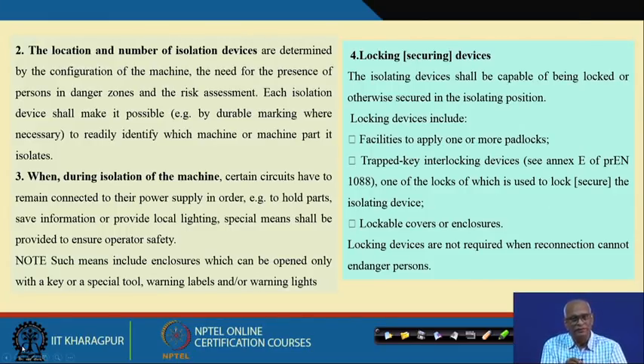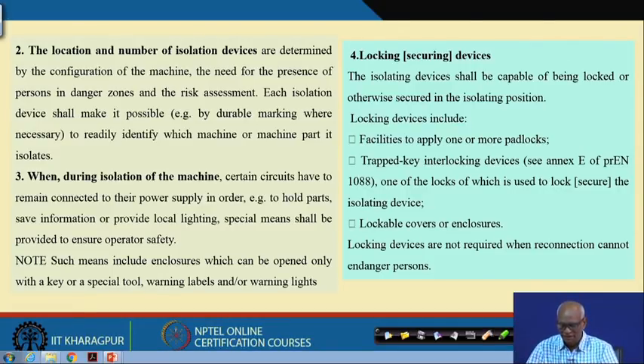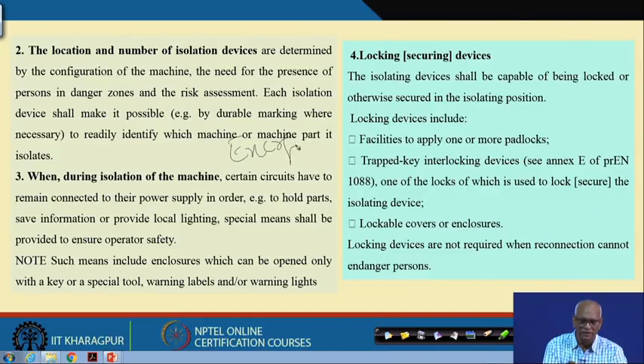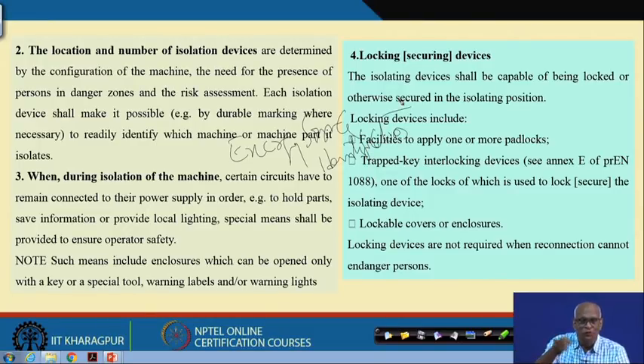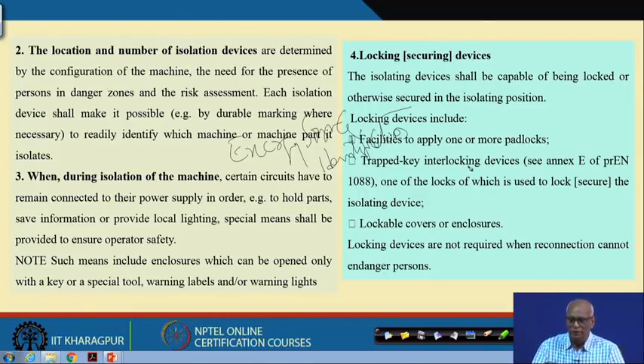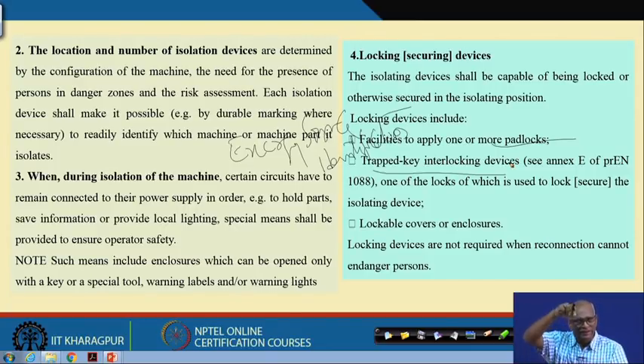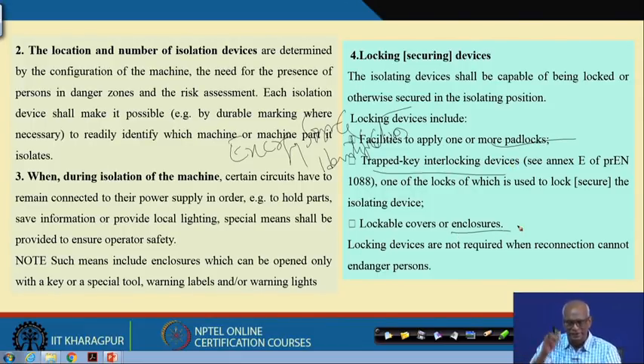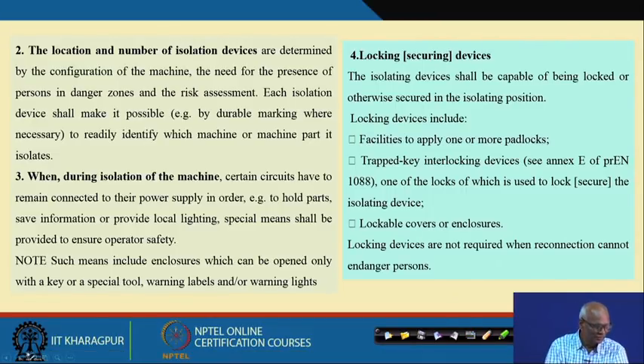You need to identify the location and number of isolation devices to be isolated — this is called energy source identification. Where to put the locks, when to put the locking devices — that is energy source identification. What are the locking devices? Pad locks, trapped keys, keys incorporated into the machine itself, lockable covers and enclosures — these are all various devices for the locking system.